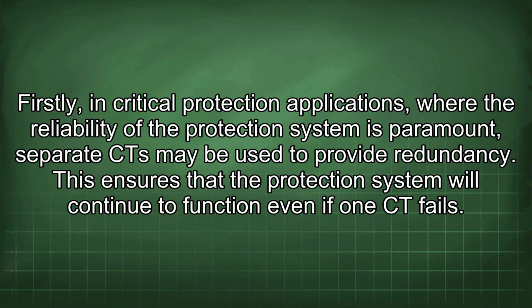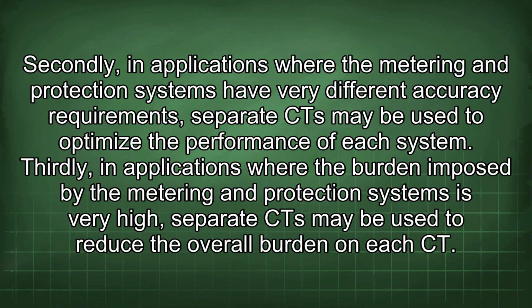Firstly, in critical protection applications, where the reliability of the protection system is paramount, separate CT may be used to provide redundancy. This ensures that the protection system will continue to function even if one CT fails. Secondly, in applications where the metering and protection systems have very different accuracy requirements, separate CT may be used to optimize the performance of each system. Thirdly, in applications where the burden imposed by the metering and protection systems is very high, separate CT may be used to reduce the overall burden on each CT.